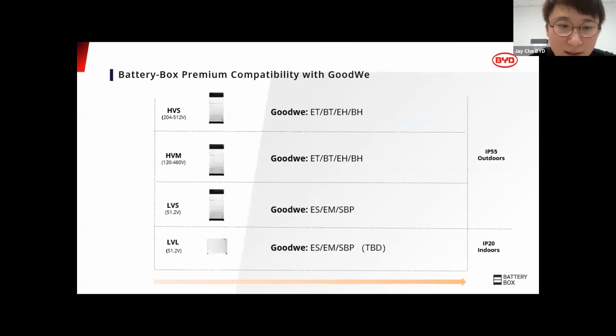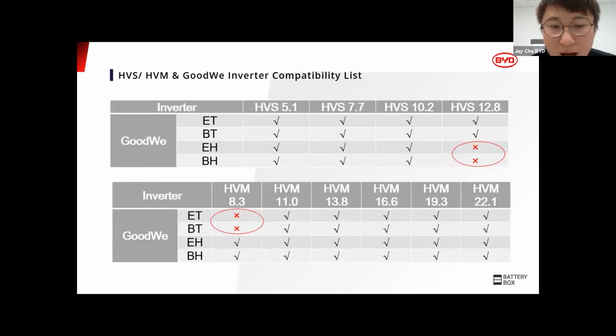Just to show you what Jack already mentioned about GoodWe inverters, so I won't cover too much - just for each battery, which GoodWe inverter is compatible. I put TBD here, but it's already compatible. GoodWe has their own compatibility list, and BYD also has our own compatibility list. For example, with GoodWe EH, the HVS 12.8 is not compatible, because the inverters have a voltage range, and the batteries we're having exceed that inverter's acceptable range. So just double check if you want to make the purchase - make sure you have the correct number of batteries connecting to the inverter.